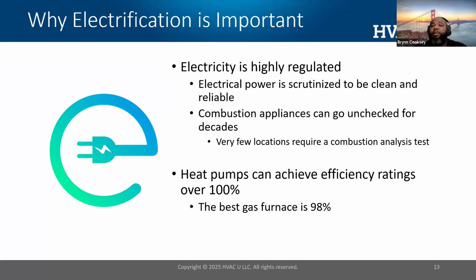Very few places in the country require some kind of active combustion testing just to verify that those combustion appliances have proper emissions. And like we mentioned, heat pumps can be more than 100% efficient. They can deliver far more energy than they consume, which beats, say, a gas furnace that can only deliver 98% of its energy that's inputted. So heat pumps have some big benefits.